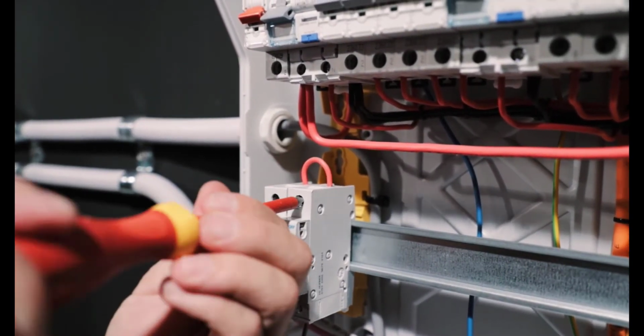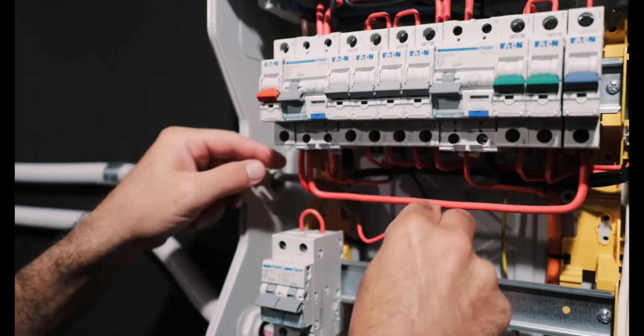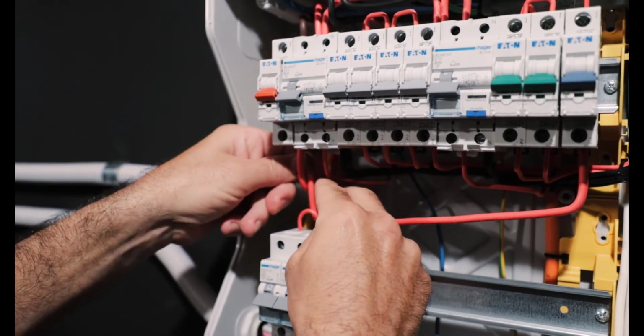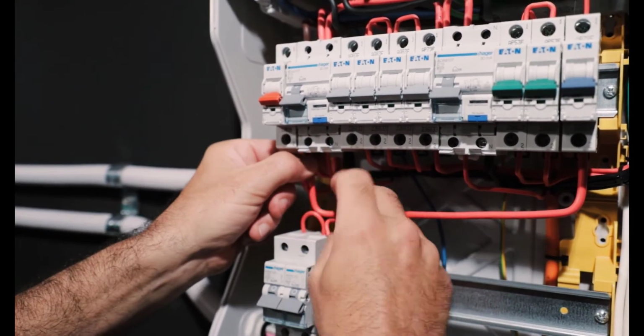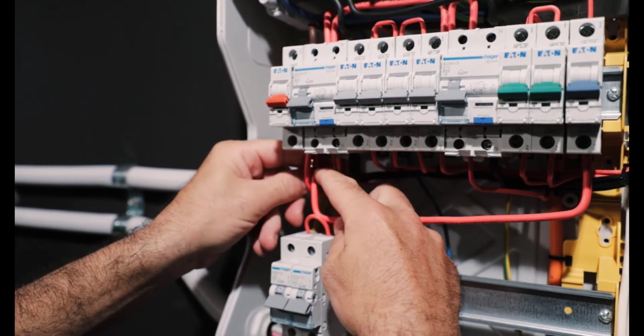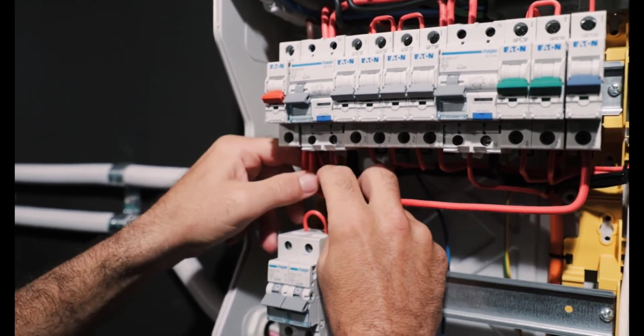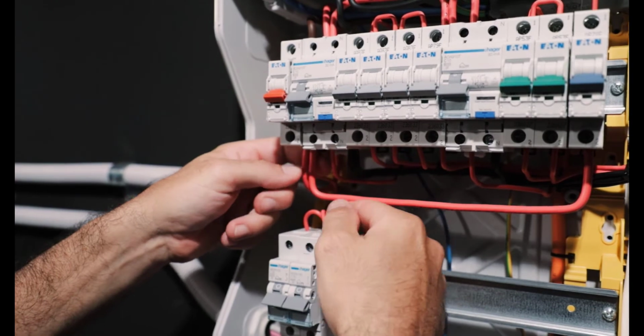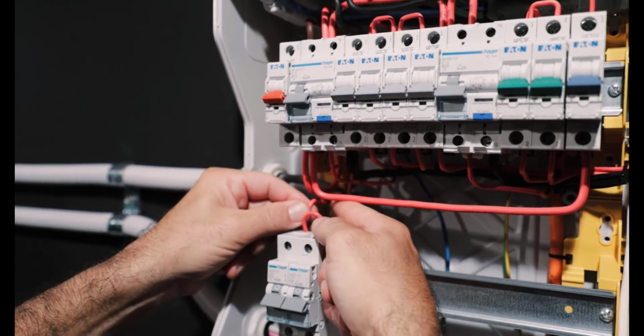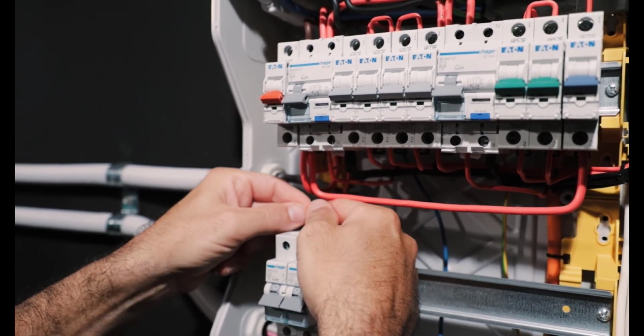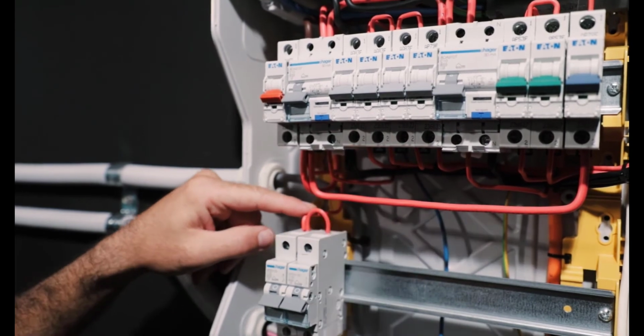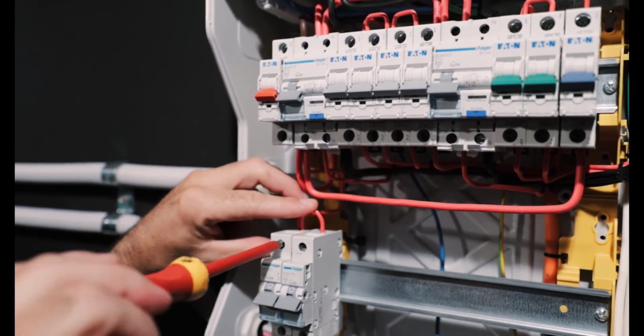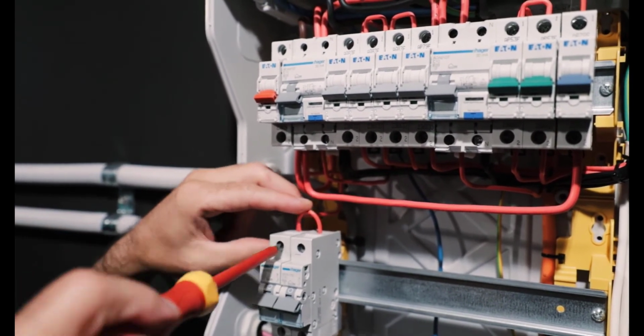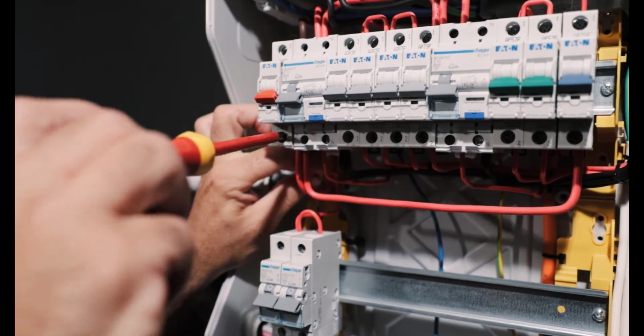However, it can be tricky if the PV, any existing PV, has been wired onto a subboard or is embedded within the switchboard somewhere. This installation here is your sort of ideal scenario because the solar is coming straight off the bottom of the main isolator coming in from the grid. We can very, very easily separate out all of the supply going to the loads.